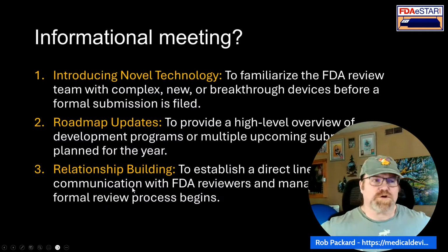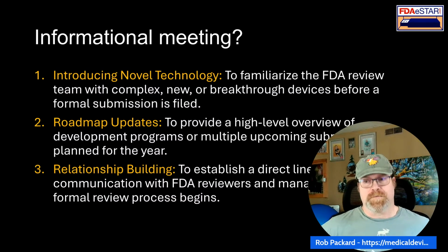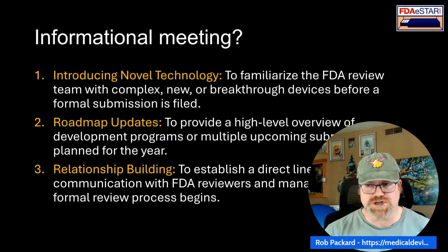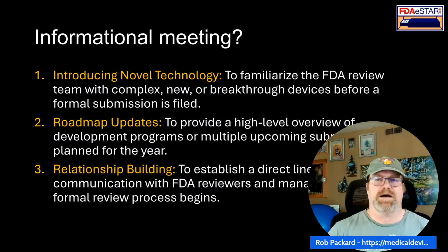Okay, next type of submission for the PreSTAR is an informational meeting. A lot of people misuse their pre-sub meetings. The purpose of the pre-sub meeting is not to say hello to the FDA, meet them and greet them and build a relationship with them. That would be more the purpose of an informational meeting, and it's unlikely that you need to do that.